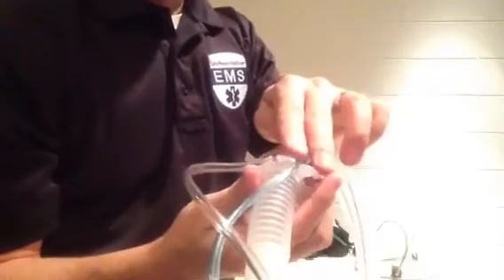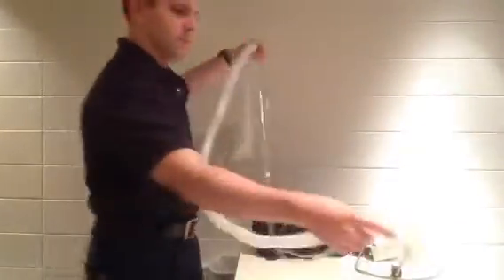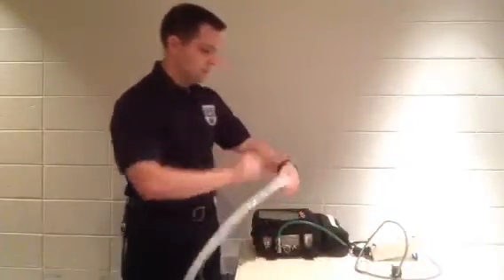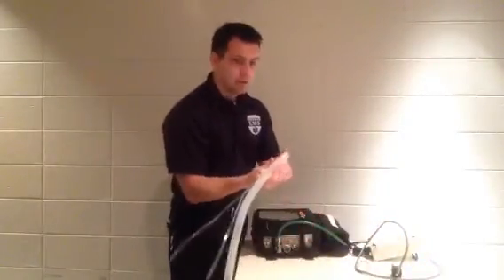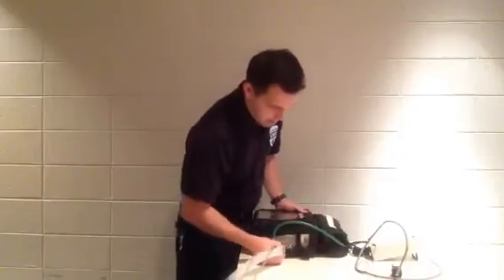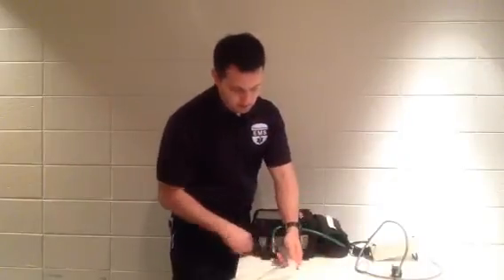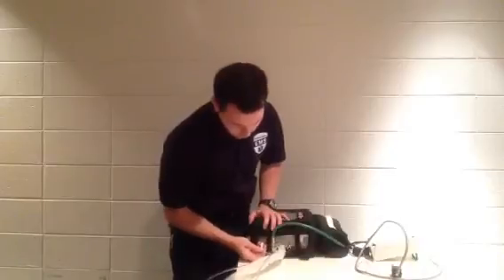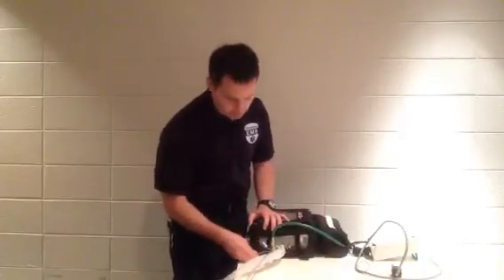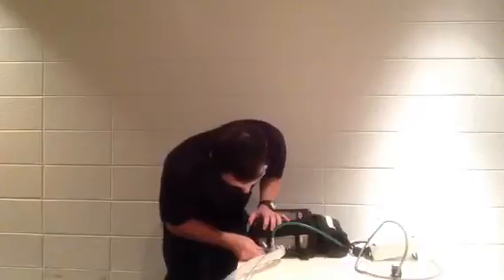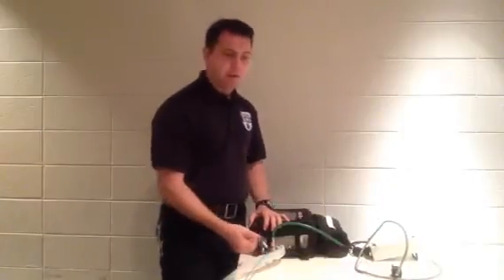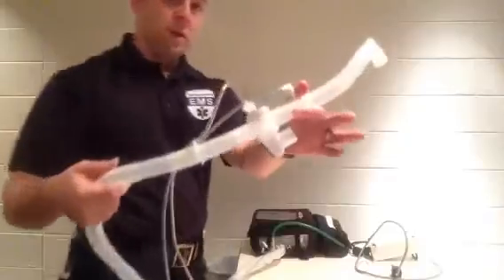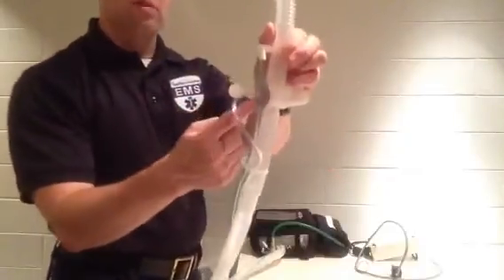It's your prox line. So we've got nice little holder positions here, so we can snap that into our line. We can run this all the way back. So very simply, we have the large vent line, fits snugly there. The clear line goes to our uncolored one, and our colored line goes to our colored line. So our transducer, our prox line, is now proximal to the patient, and our exhalation valve is actually at the exhalation valve, tracing all the way back.